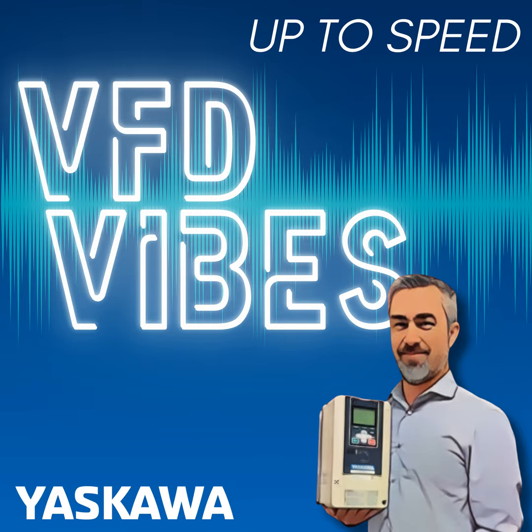And I'm going to tell him, okay, there's no signal on A1. No, controls is sending me 10 volts. Those other 9 drives are running at 60 hertz, but we got nothing here. All right, let's take that jumper wire and put it from plus V to A1. Plus V is an onboard 10 volt signal that is going to send 10 volts to A1 and run it at 60 hertz. He'd put that jumper wire in. My motor just started, and U113 says 100%.